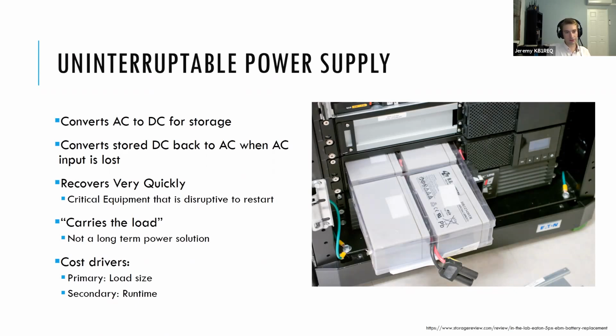Our cost drivers for UPS, primarily it's load size. The more power you need from this UPS, the more it's going to cost, just because you're going to need more and more expensive electronics. And then once you're in that load size, the amount of runtime you need is going to scale that cost up and down as well. Once you have a load size, you're essentially paying for batteries. So it doesn't increase as much if you're at the same power level, but it still will increase your cost, if you say, okay, I need a UPS that's going to run 30 minutes versus 4 hours.